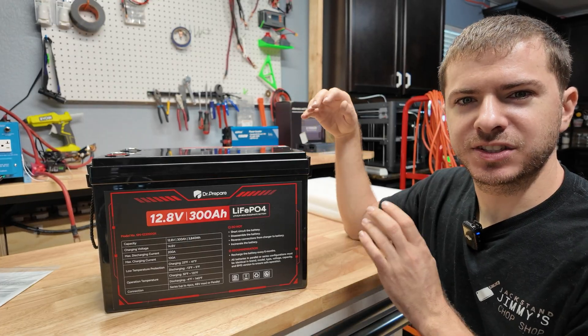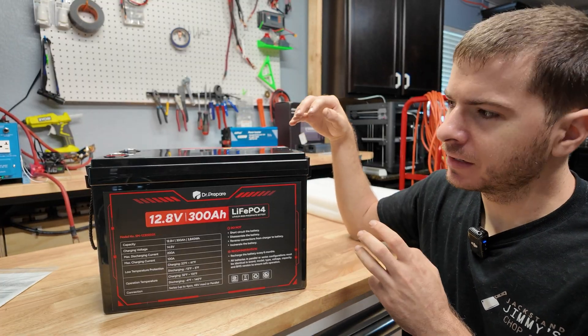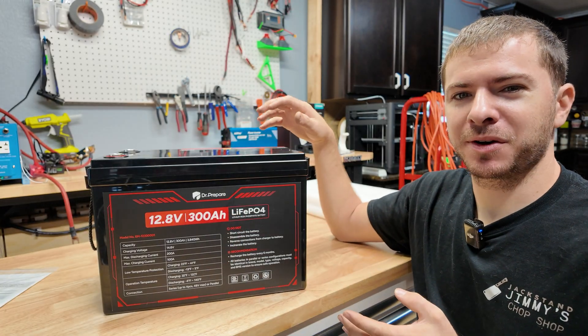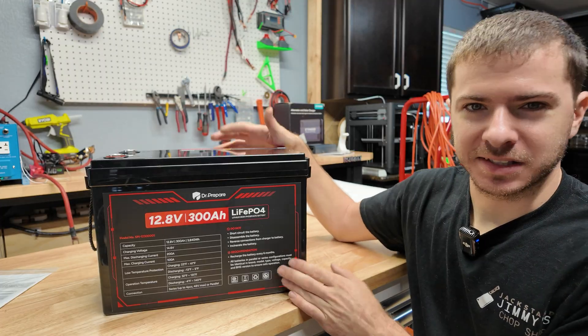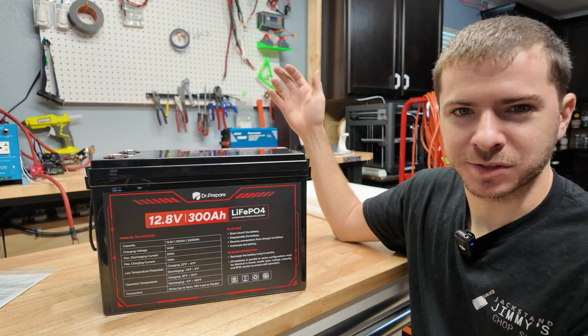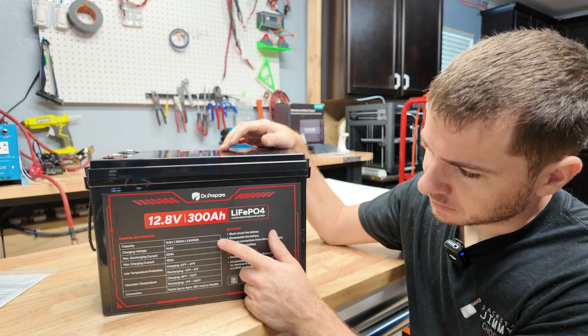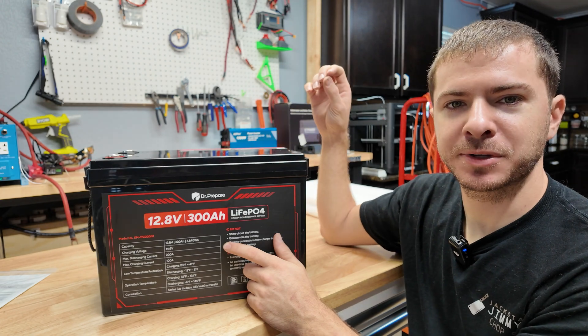Today we're going to be taking a look at and testing this Dr. Prepare All Volt 300 amp hour lithium iron phosphate battery, made by a company called Dr. Prepare. It's kind of funny because a lot of battery names and manufacturers out there are crazily named. This one's rated at 12 volts, 300 amp hours, with a capacity of 3,840 watt hours and a max of 200 amps continuous discharge current.